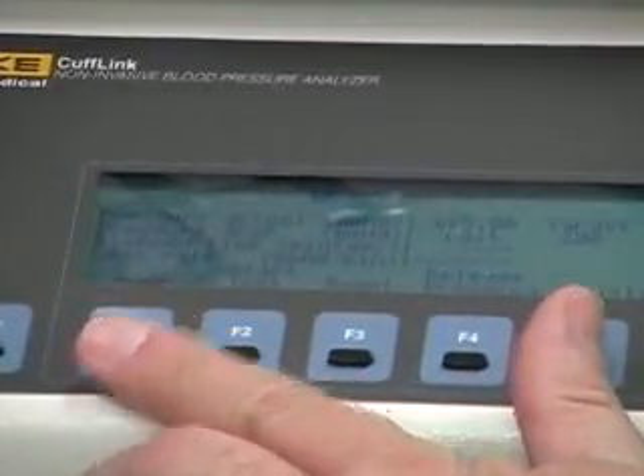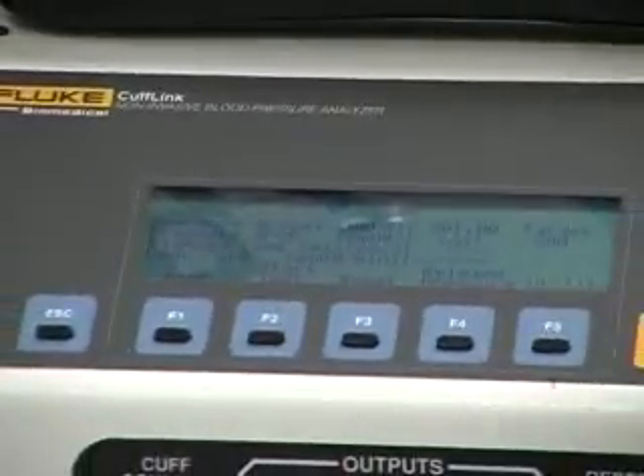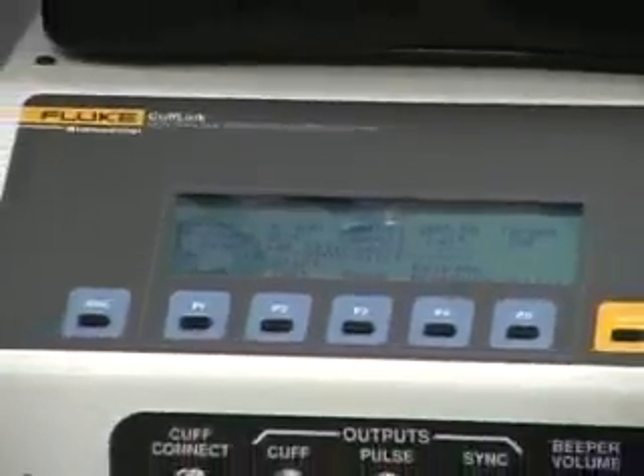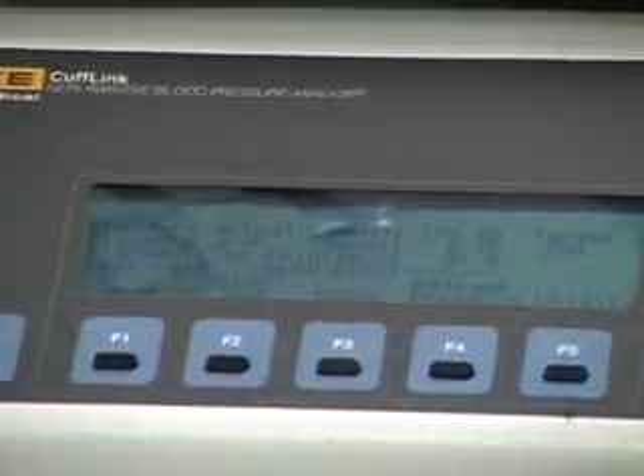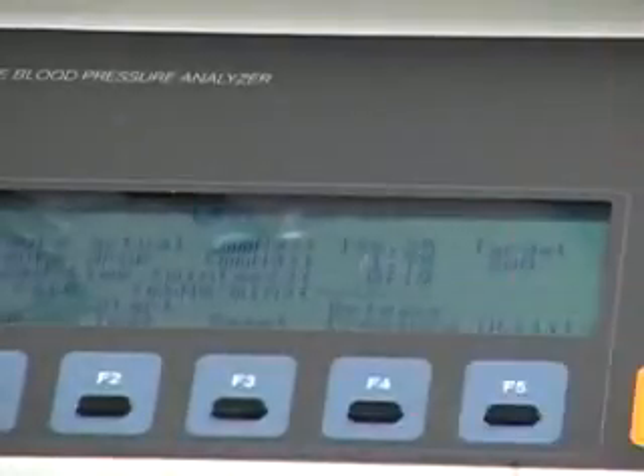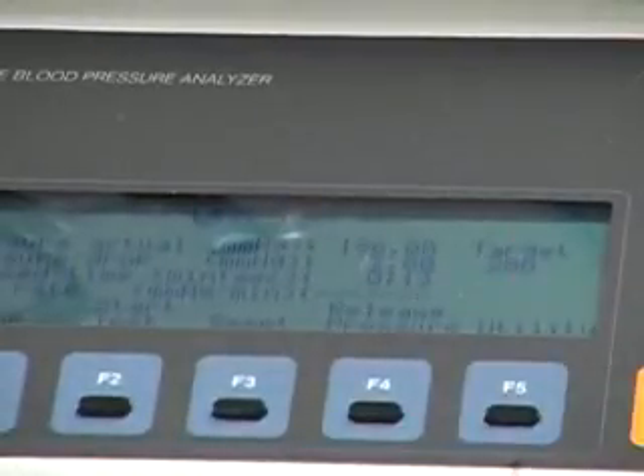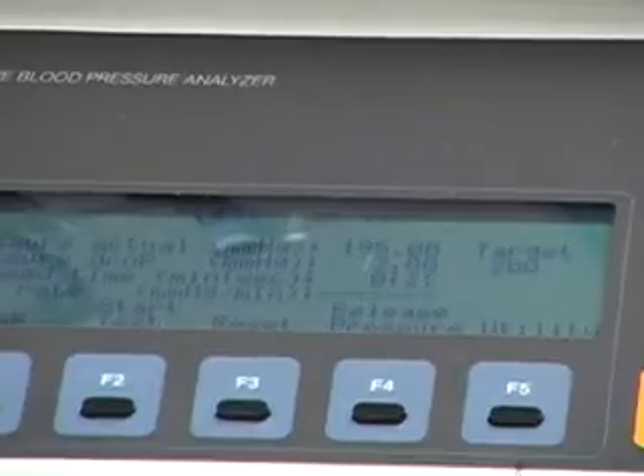Bring the pressure up, something over 200. And I've got it at about 203. Just waiting for it to stabilize. And now we can start the test. And now it's just reading the pressure and looking for the pressure changes. Then after 1 minute, it'll give you a leak rate. So again, it's a real good little test, making sure all your accessory items are in good shape. Also, it's a good test on the Cufflink itself, making sure that the internal tubing is intact.